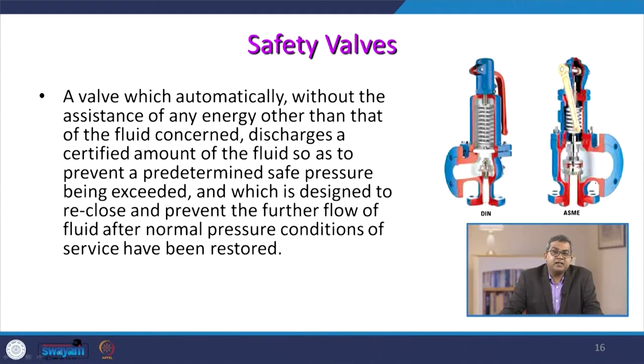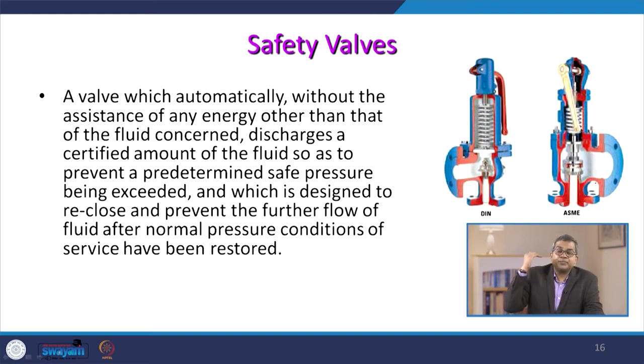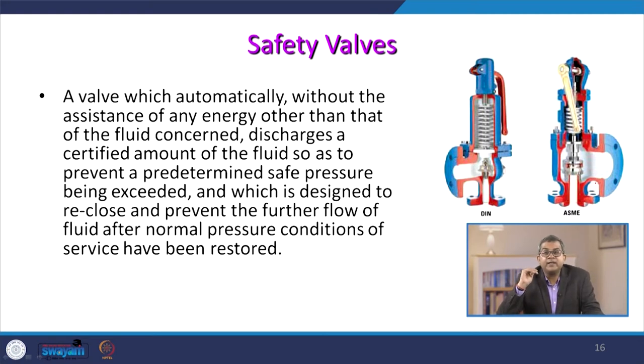A safety valve is a valve which, automatically and without the assistance of any energy other than that of the fluid in question, discharges a certified amount of fluid so as to prevent a predetermined safe pressure being exceeded, and which is designed to reclose and prevent further flow of fluid after normal pressure conditions of the service have been restored. So when pressure is beyond the working pressure the safety valve actuates, and when the original desirable pressure is restored, the safety valve should automatically close so that precious steam cannot escape beyond the periphery of the boiler.